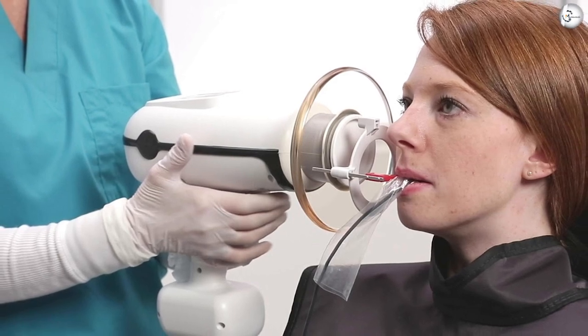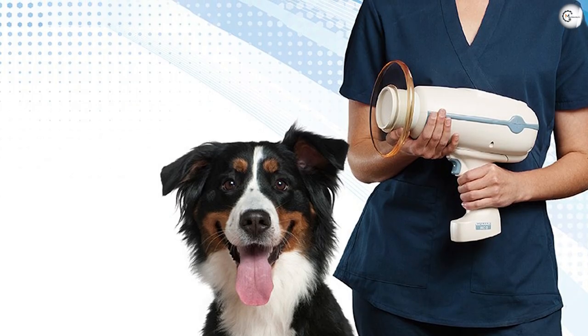Nomad Pro 2 utilizes the latest in X-ray technology: a 0.4 mm focal spot plus a 60-kilovolt DC X-ray generator that consistently delivers exacting, repeatable exposures.